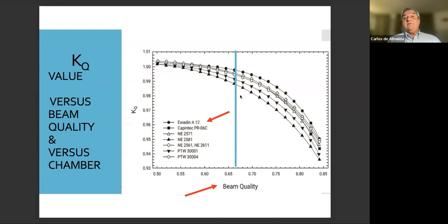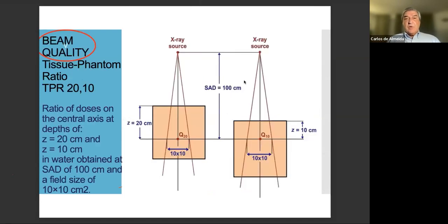You can find this in several publications like TRS 398, and for some chambers that were developed after 398, you can find it in the literature. What is important is to define this beam quality, as you see. This is, as I said, about here 6 MV, then 10 MV and 25 MV and so on. On the next slide, as you know, the beam quality is defined by the tissue phantom ratio, which is a ratio between two readings: a 10 by 10 field size at 20 centimeters of water for the same SAD, and then a 10 by 10 at a depth of 10 centimeters. The ratio 20/10 is what we call the TPR, and that is what we relate to the quality of the beam.